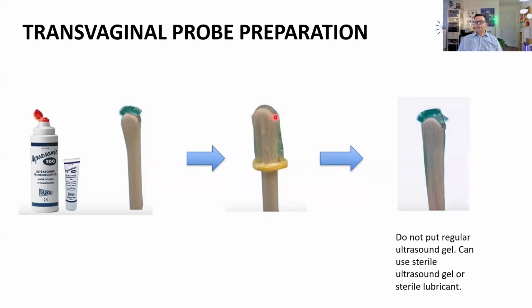Air will make the image look bright. You'll see a bright area with a black acoustic shadow. So we don't want that, and make sure that there's no black zone over there. And then we can also put a little bit of specialized, not regular gel, but a sterile ultrasound gel or a sterile lubricant outside the sheath to provide a little bit of lubrication before inserting the transducer into the patient. Please do not use this gel, because it is not sterile for that application and can cause infection. So we definitely don't want to use this unless you have a sterile one.